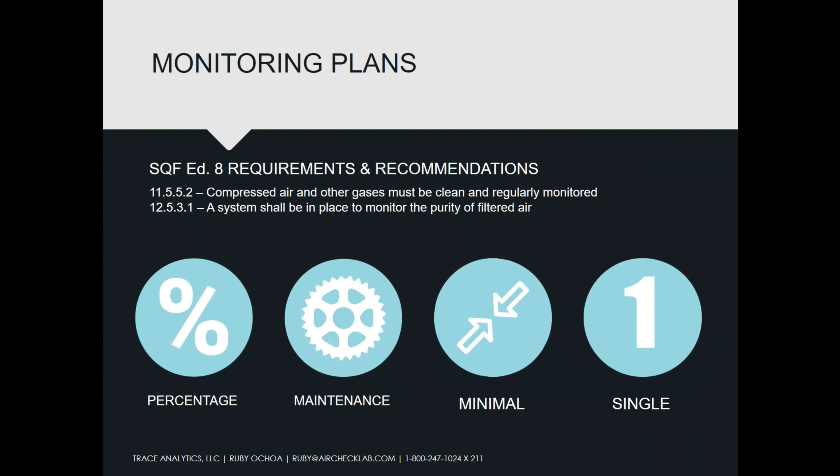The one that I like very much, especially that lines up well with SQF, is that you would take samples based on your maintenance schedule. So if you change those filters out every six months, we would recommend taking a sample right before you change the filters — that gives you your worst case scenario, showing how bad or dirty your air got. I also suggest taking a sample immediately after, just to make sure the filter isn't damaged and was placed properly, and that purchasing didn't change the specs on your filters. These things have happened out in the real world.